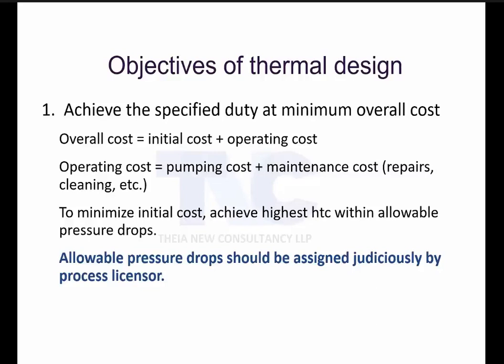And a very good engineer, remember, should judiciously use the allowable pressure drop. When you do a simulation, you will know this exchanger has an allowable pressure drop of 0.5 bar. Try to use at least 0.45 bar from that exchanger. If you have 0.2 bar, at least use 0.18 bar. Use the majority of your pressure drop and design your exchanger, because the more the pressure drop, the higher the heat transfer coefficient, and the smaller the size of the heat exchanger.